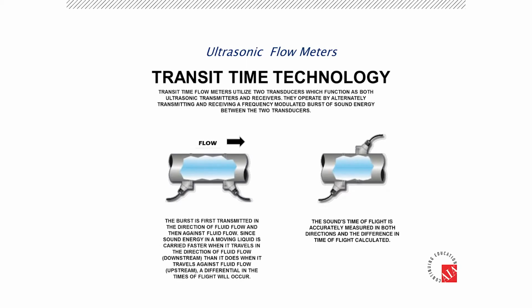It's like walking against a headwind. It's harder to walk against the wind than with the wind. So the faster the flow rate, the greater the differential of time. Not to be confused with an ultrasonic Doppler flow meter, which you don't see too much today, but long ago, a Doppler flow meter kind of works like radar. It bounces off suspended particles.